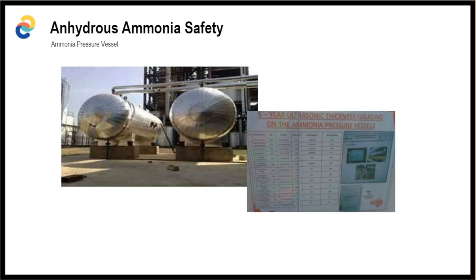Also, some local guides require a permit. Normally here it's an annual one, so a pressure vessel should only be used with an approved permit. Also, the permit should be displayed in a conspicuous location, so easily seen, so that people know by inspection that the vessel is still good to use.